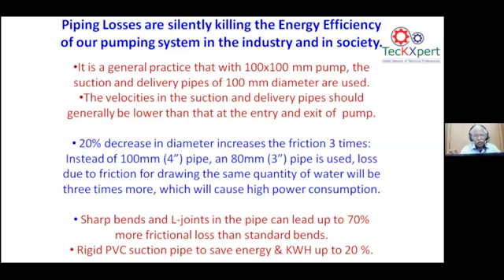Instead of a 4-inch pipeline on the pump delivery, over a few years it becomes 3-inch, which means definitely the friction increases by 3 times. So this is a loss, and definitely the kilowatt consumption also increases.